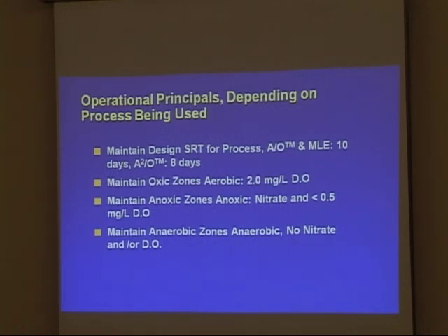Then your oxic zones, you want to make sure, like I said, I don't like to see less than 2 milligrams per liter of DO. However, when we were doing the blower testing, it was interesting because we had the cutoff at the very end, your last 2 DO probes.